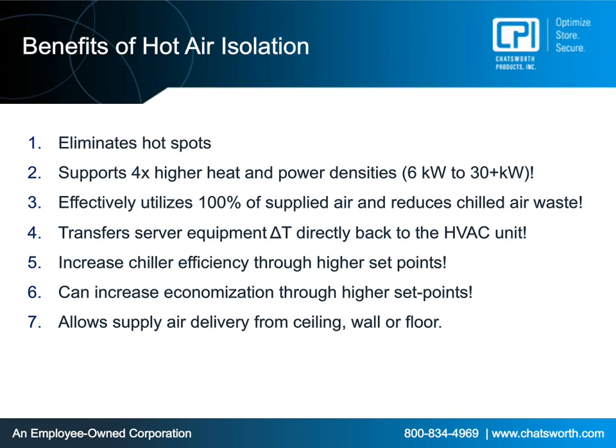And then we're going to take your delta T, which is your change in temperature. So you start with one temperature, it goes through the server, and you have a hotter temperature on the backside. We're going to maximize that delta T so you can get the most out of your HVAC unit. So 1 to 4, that's kind of like the starting point.